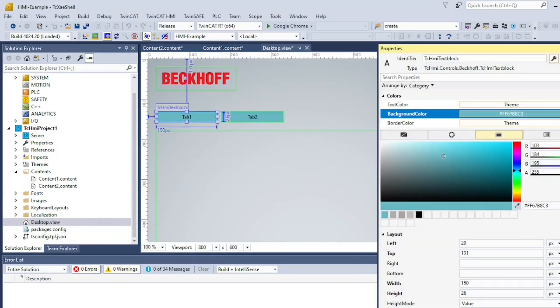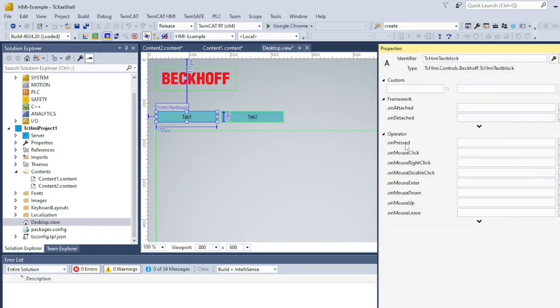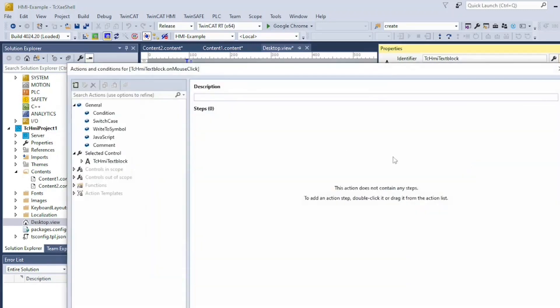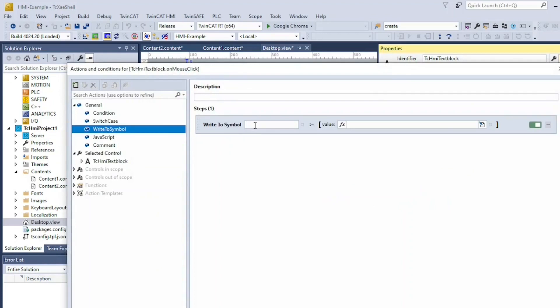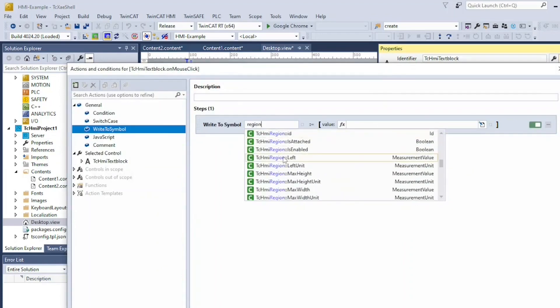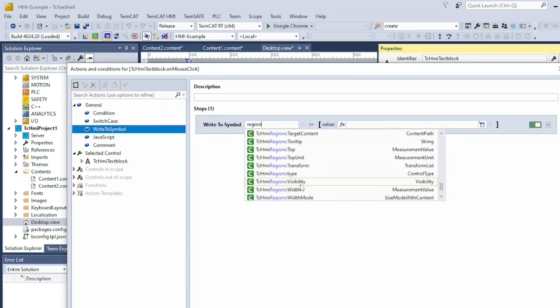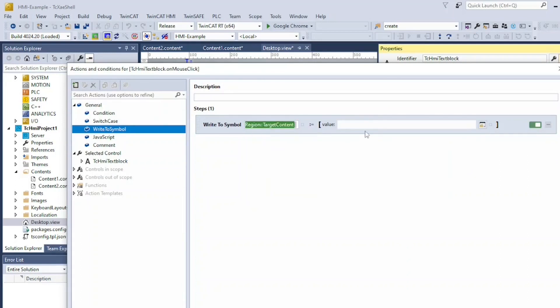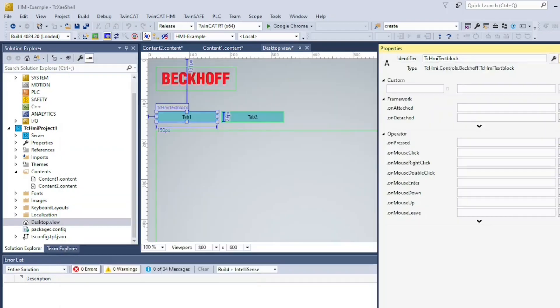Back to my tabs, I'm adding logic to the on-mouse click event. Then I need to assign my content path to the target content of the region: TcHmiRegion::TargetContent equals contents backslash content1.content. Upon clicking on the tab, the target region content will be set to the corresponding content.